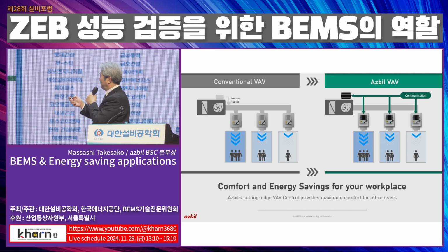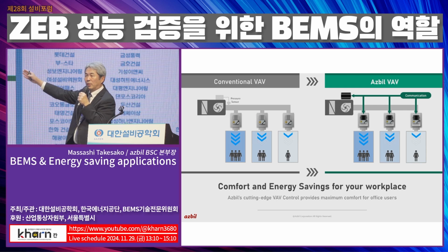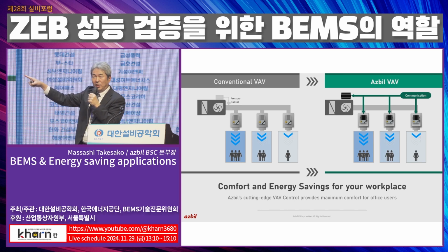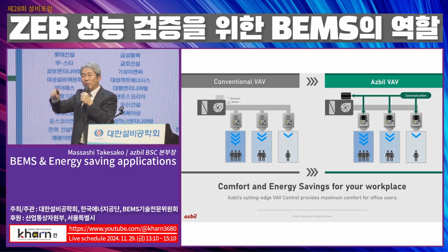We get the necessary information from each VAV controller, and again, the key to energy saving is how to minimize the static pressure of the fan. To maintain a constant static pressure is wasting energy, because the load is always fluctuating.